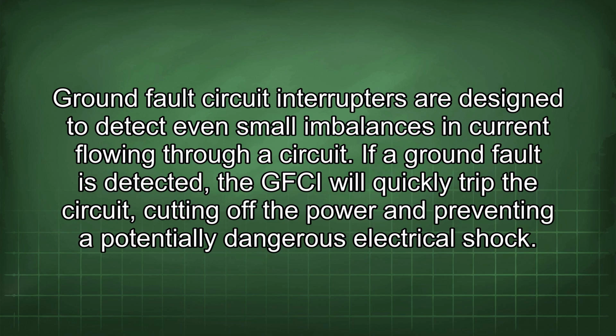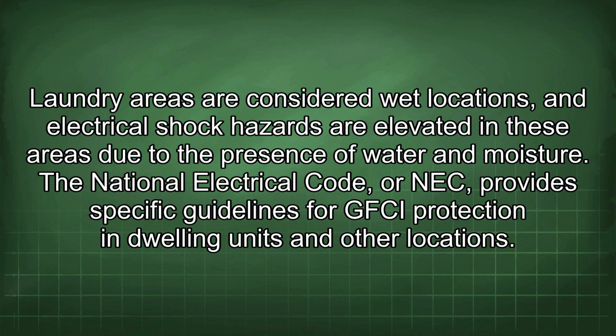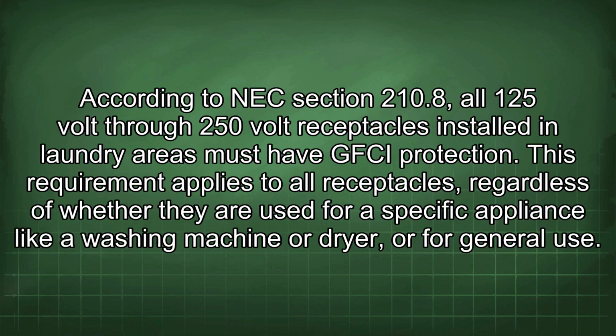If a ground fault is detected, the GFCI will quickly trip the circuit, cutting off the power and preventing a potentially dangerous electrical shock. Laundry areas are considered wet locations, and electrical shock hazards are elevated in these areas due to the presence of water and moisture. The National Electrical Code, or NEC, provides specific guidelines for GFCI protection in dwelling units and other locations. According to NEC Section 210.8, all 125-volt through 250-volt receptacles installed in laundry areas must have GFCI protection.